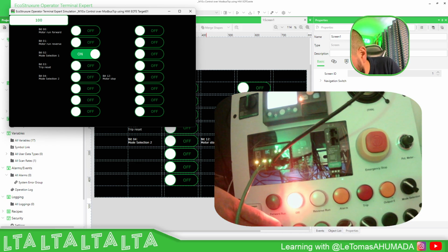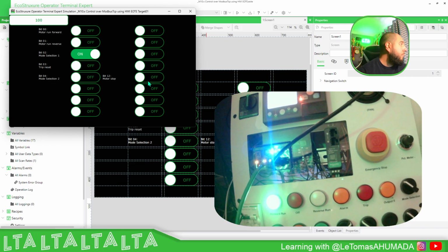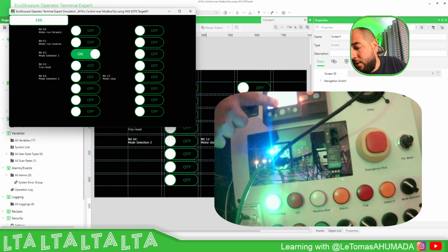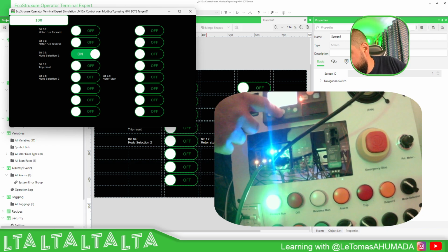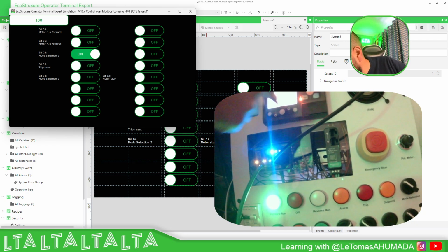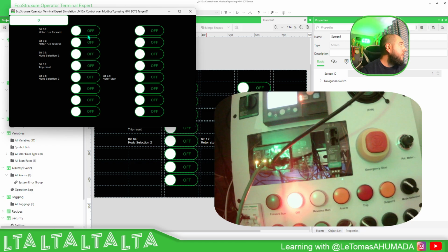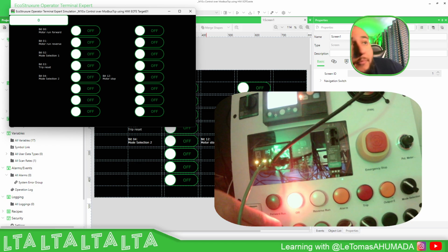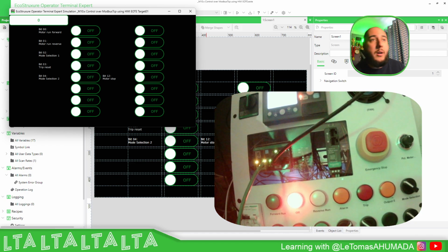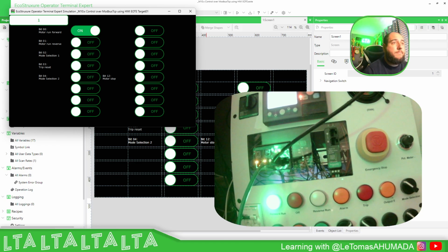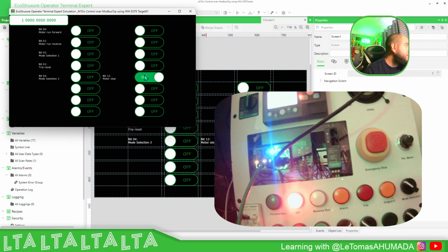Now if I try to run from here and stop it from here, it will not work. You will see here on the display stop error detected, because it's trying to do something that it shouldn't be using. Then I'm going back and stop it, which is fine. Now if I change this and make the run from here, it will not work. I'm pressing it, and here it says stop error, no access, and then from here it's working fine again, and stop it.